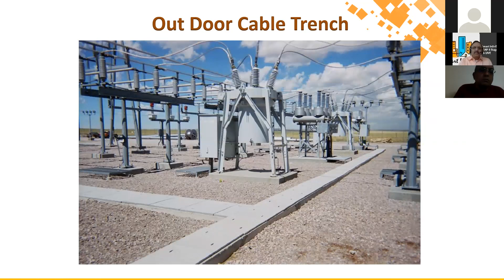So this is how the outdoor cable trench looks. We cover the cable trench with precast slabs, because all these require maintenance. Earthing is different. For earth mat maintenance also, you will be able to remove the slabs easily and do it.